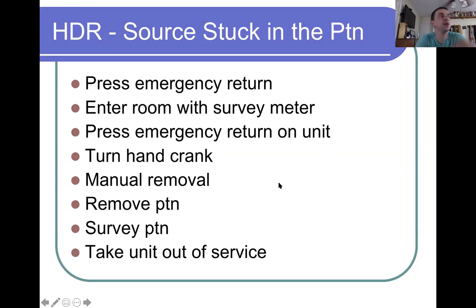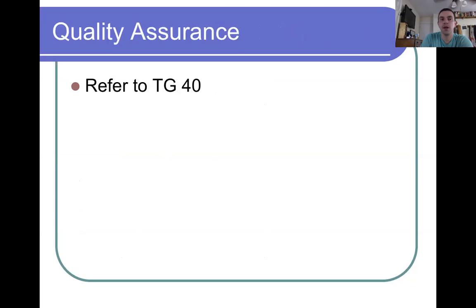And we have what we call a doghouse. Inside this heavily shielded room, we have a little more heavily shielded closet. In the worst case scenario, where the automatic retraction fails and the manual retraction fails, we are able to just grab the source and toss it into this small shielded closet. It's not perfect shielding, but it will significantly reduce the dose rates, to get the patient out of there and take stock of the situation and how to handle it. But yeah, these are much higher stakes than a lot of the low dose rate stuff, because you can get very harmful doses very quickly.